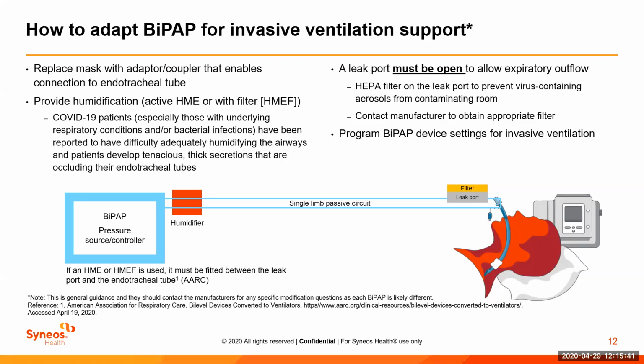So we take this device that we're familiar to call BiPAP, whether it be John's BiPAP machine or Harry's BiPAP machine. If it supports BiPAP, it'll support a breath. We then connect it to a humidifier because we have to give active humidity for the secretion mobilization. But let's stop for a second and recognize that there's one tube going from this BiPAP device to the patient. Mechanical ventilation went years ago to two limbs, a dual limb circuit. And the reason for that is we needed some specific control to monitor exhale tidal volumes. The machine started getting a little bit more sensitive. And so if we could measure flows on the inspiratory side and expiratory side, we can be very sensitive and respond to patients when they're spontaneously breathing.